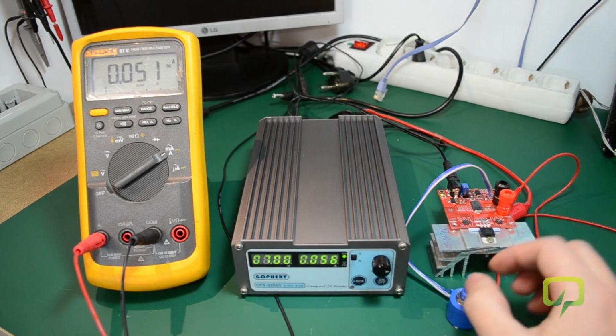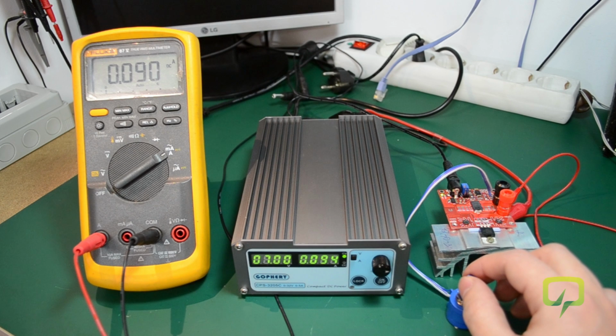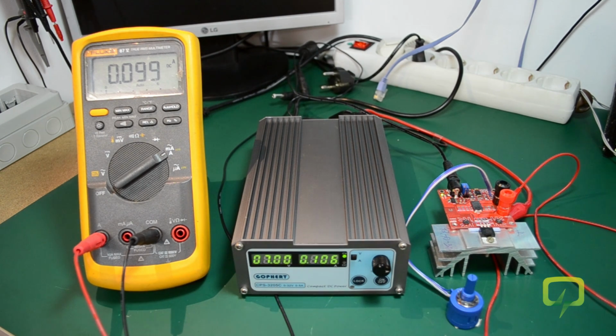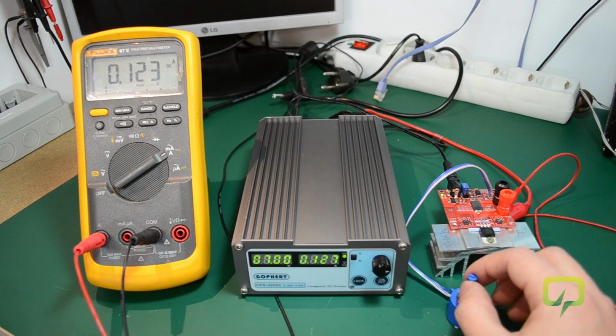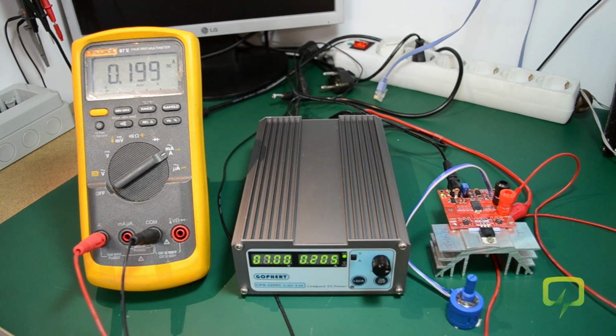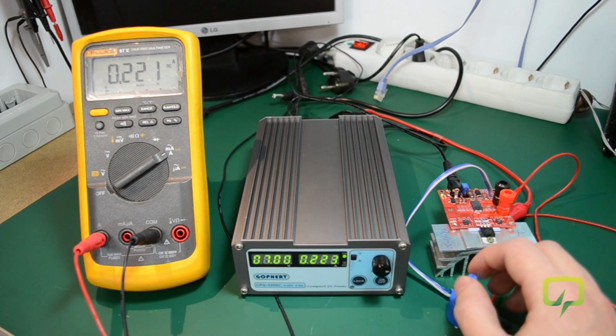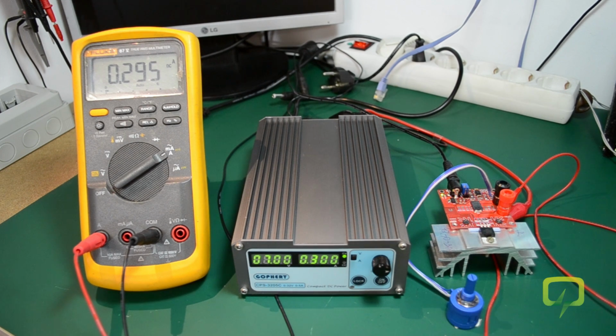Next, I'm going to adjust for 100 milliamps. I'm looking at the Fluke 87, and for 100 milliamps it seems the power supply is showing exactly the same difference as for the previous measurement, that is 6 milliamps extra. Let's check the accuracy for 200 milliamps. It seems it's almost the same difference between the measurements, 5 or 6 milliamps. Let's go at 300 milliamps. Close to 300 milliamps, the amp meter on the power supply is showing exactly the same difference as before when compared to the Fluke measurement. That is 5 or 6 milliamps extra.